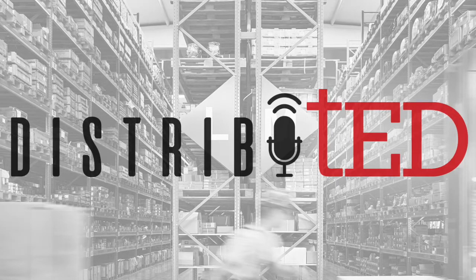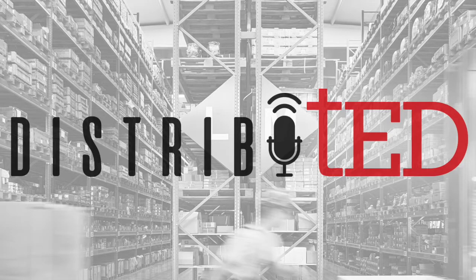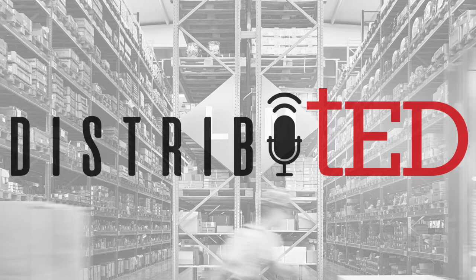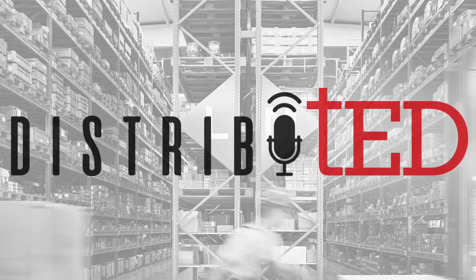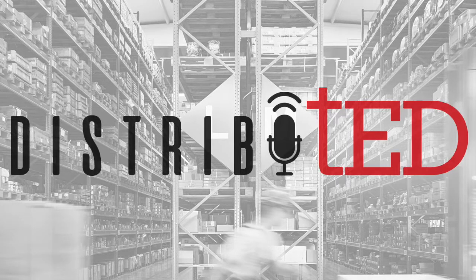In the specific area that talks to reconditioned equipment, there was a change made starting last cycle in the 2017 code, where we created this reconditioned equipment section. In there, we have language that says you have to mark the product you recondition with who did the reconditioning. I look at it as transparency, and that went in last cycle. So basically, if you recondition a piece of equipment — whether switchboards, motors, or whatever — you have to put your name on it, whatever that organization's name is. You're also maintaining the original manufacturer's labels; there's no requirement to remove them.